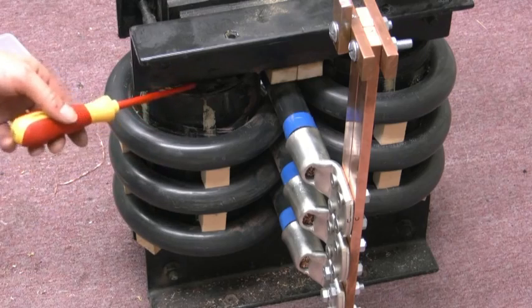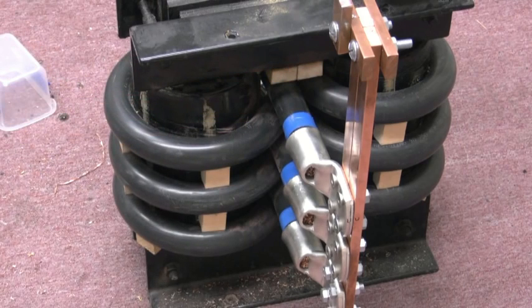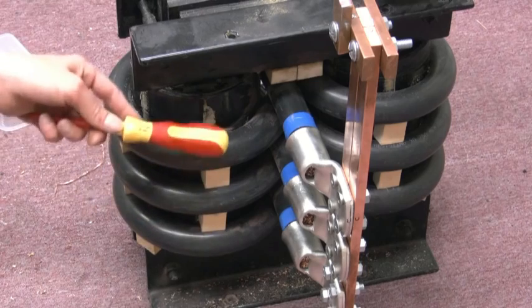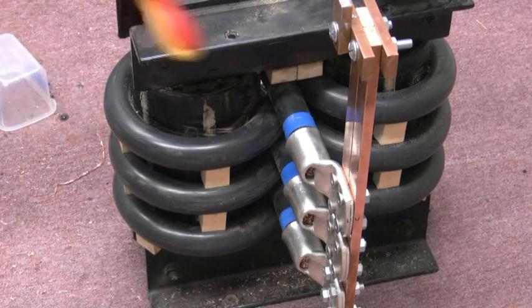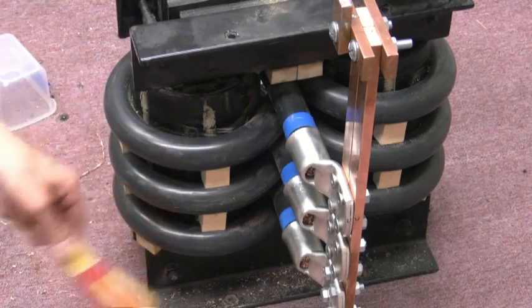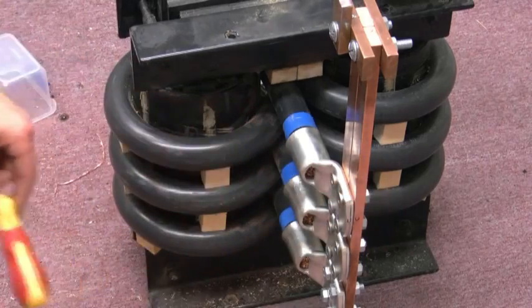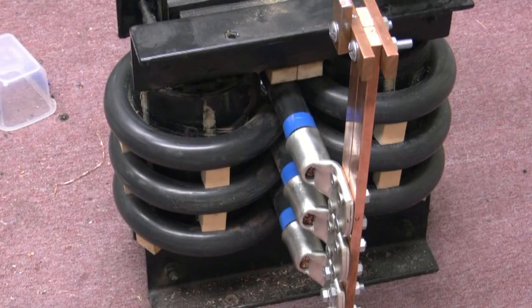We've got 120 volt winding, another 120 volt. Both of those are in series, so it runs on 240, and each one of these 400mm cables goes round in a figure 8. And then there's 3 of those all in parallel, so you've got one output there and one the other side. Voltage on short circuit currents probably about half a volt, and obviously off load probably 4 volts. So if you take half a volt and we've got probably 15 kVA, then 30,000 amps isn't unreasonable.